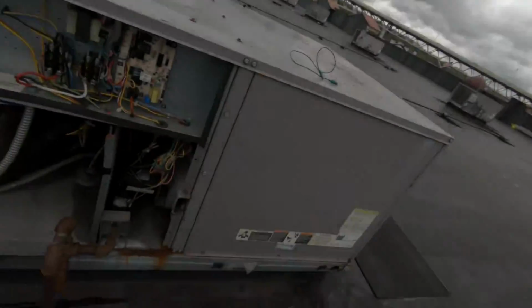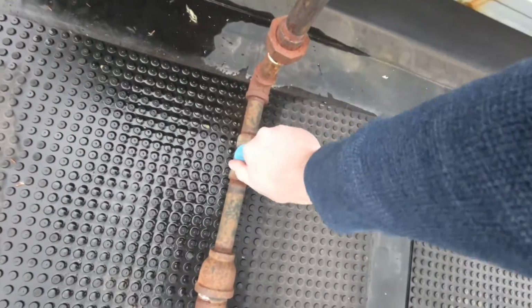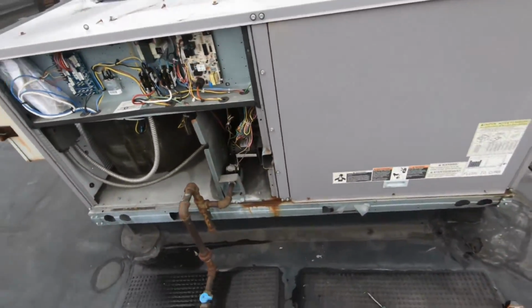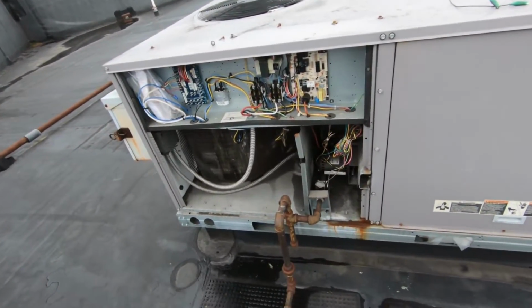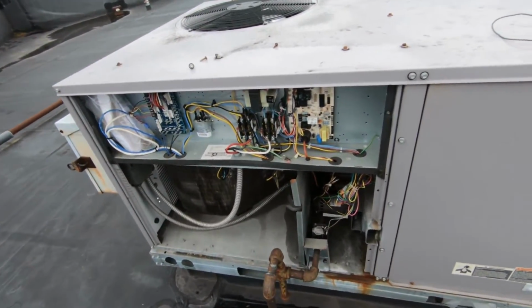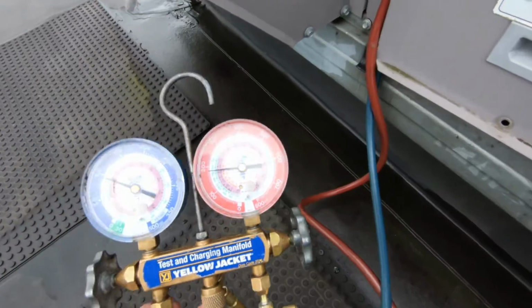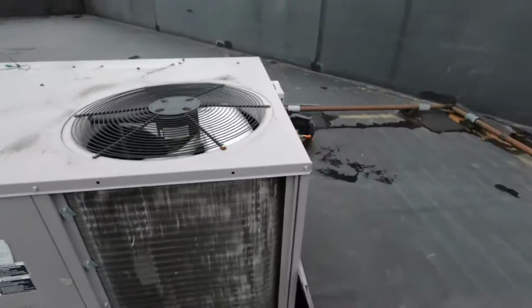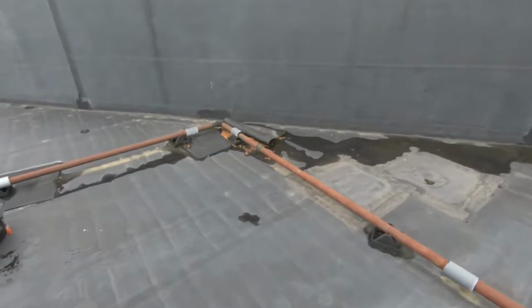Well, it fired up, but boy, that combustion blower definitely needs replaced. So I'm gonna go ahead and... gas valve's good. Definitely needs a heat exchanger, needs a combustion blower, and all the other parts I listed. So pressures don't look too bad.